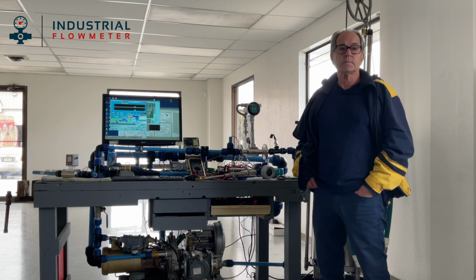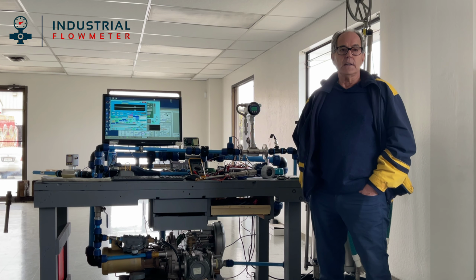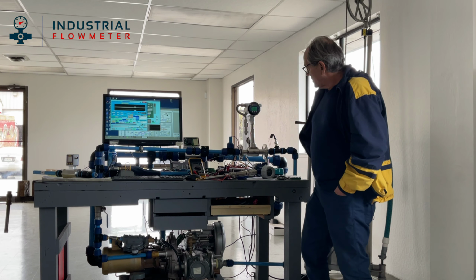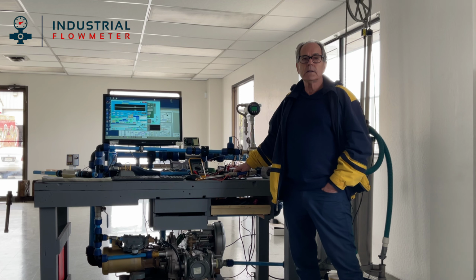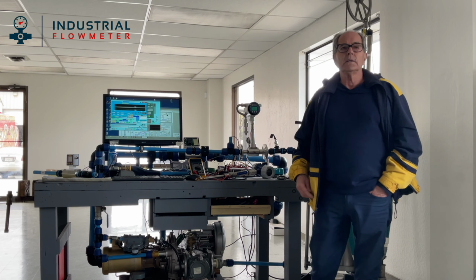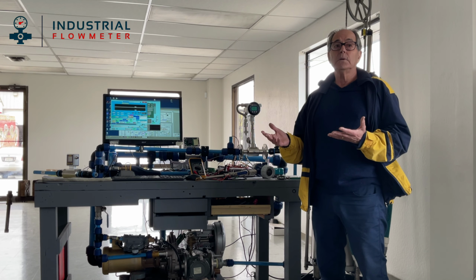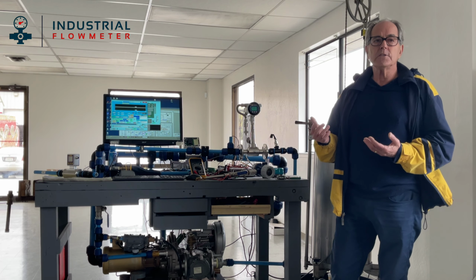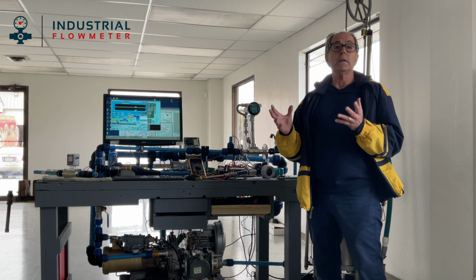And just one question, when you say time domain, I remember that anything that has an output that's frequency is in the time domain, is that right? And if something has an output that's in volts, that's the amplitude domain? I don't know what domain it's called. Doesn't matter. But by time domain, all we mean is that we have an output that's a frequency, and we're mapping a frequency to a flow rate. Yeah, time domain is pretty nice because it's simple to trace back to something, because crystal oscillators are cheap. HP reference standards are cheap, relatively speaking.